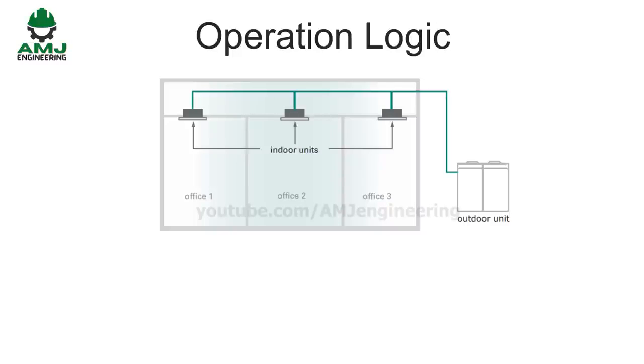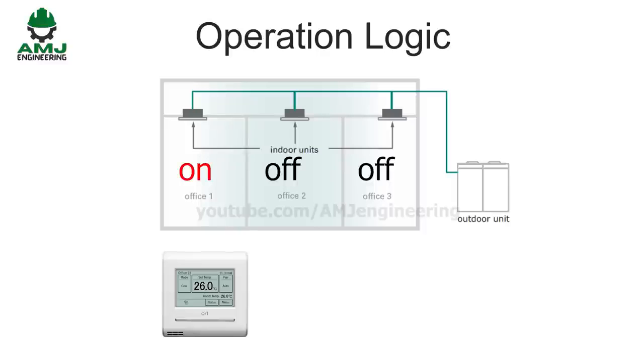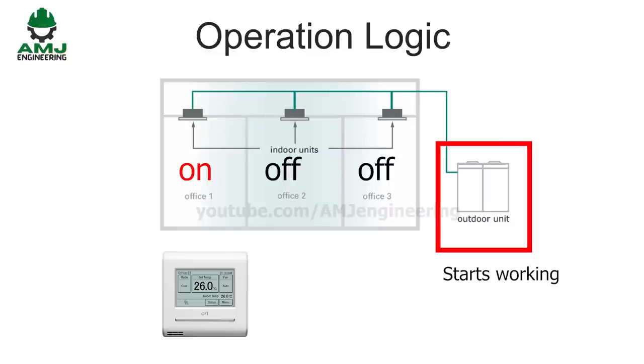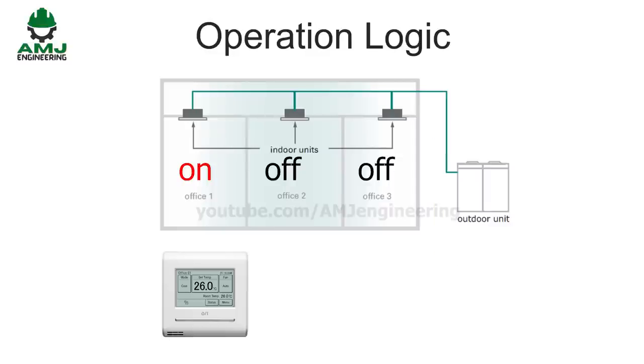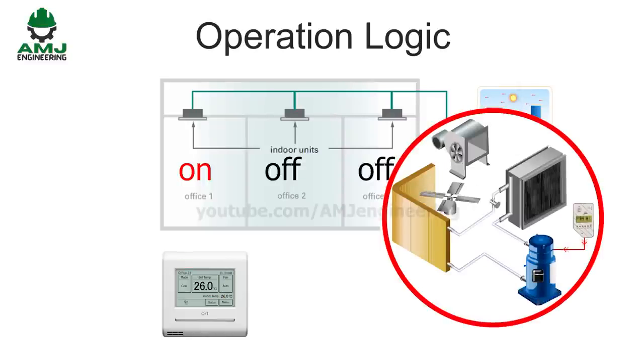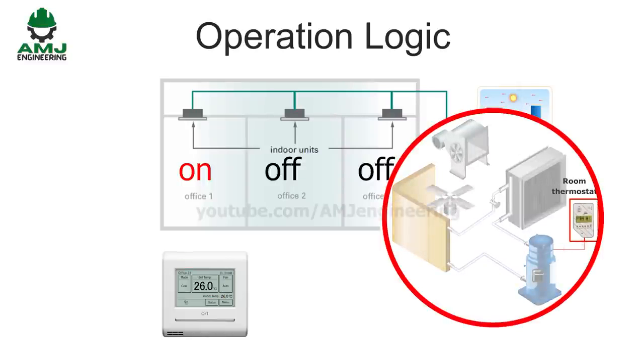At the beginning, the system is in a standstill condition. This means everything is turned off. Once a user turns one of the indoors on by its local remote, the outdoor gets notified regarding it, and starts working. At this point, it will examine the outdoor temperature conditions and the operating indoor requirements such as operation mode and set point temperature, and will operate the compressor at the exact level required to comply with the indoor requirements.